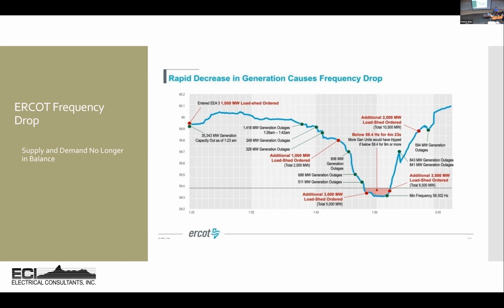Meanwhile, they're also losing generation as the plants are tripping offline. When they finally get down to 1:53, they're shedding another 3,000 megawatts they're ordering to be shed. A couple minutes later, they ask for another 3,500 megawatts to be shed. So basically with this particular ISO, they had about 5 minutes. If they had operated at 59.4 hertz for 4 minutes and 23 more seconds, more generators would have tripped offline, the frequency would have gone down even more, and the system basically collapses in on itself. So bad things happen. That's why we want to make sure we keep everything in balance with each other.